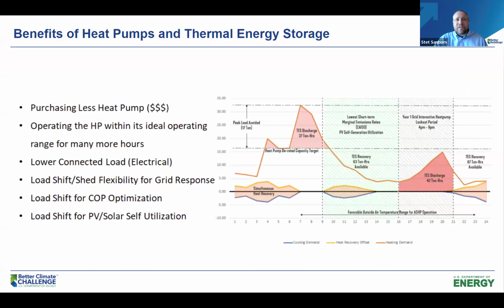So with that, I just want to reiterate, looking at these integrated strategies, whether it's plug load, changing what type of equipment you plug in, or finding the right heat pump that can do heating and cooling off of the same electrical supply, those are all ways that are going to help reduce that cost, reduce the barrier to entry to doing a greenhouse gas reduction on your site, your property. But there's a whole lot of other really great benefits that these technologies can bring together. Thermal storage plus a tiny heat pump gives you a lot of load shift capacity. Your heat pump's actually going to run more efficiently because it's at its design load, and it's going to let you self-utilize any PV that you're generating on site.